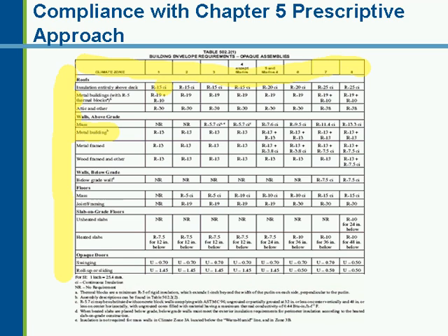We'll have a walls below grade category. And you'll see on walls below grade the NRs that go across, and in most cases, except in climate zone 7 and 8, you will not have to insulate a below grade wall. Floors over an unconditioned space, you'll have an option between either a mass floor or a joist frame floor, so there will be frame cavities to put in insulation.